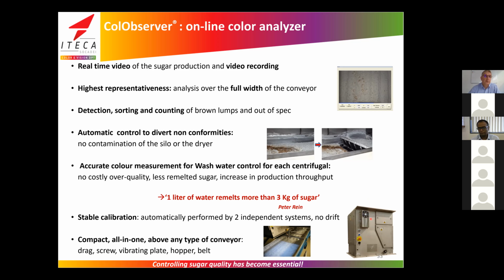You also have to take care about the cleanliness of the window, the internal calibration plate, and the external calibration plate. When using the system on the screw conveyor or belt conveyor, we have another calibration plate integrated in the spacer located just below the system. If you take care about cleanliness and temperature, the system will work well.